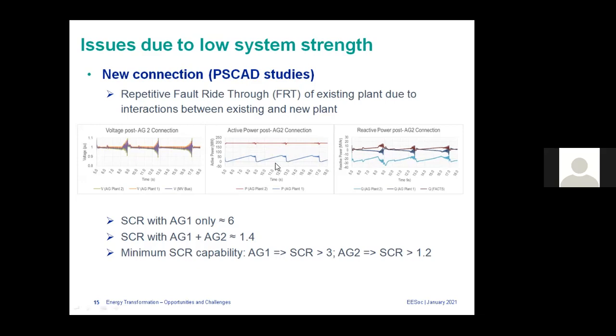You can see in the middle plot that when you model it, the second plant can maintain stable operation. But the first plant goes through repetitive fault ride through. What's happening is that when it is generating, it finds the total SCR is less, so it blocks its operation. Then the megawatts drop, and the system seems to be fine, because what inverters do when there is a system voltage issue is block themselves. When the system voltage recovers, they start to operate again. So it blocks, then it only sees the other plant, the system voltage becomes better, and it thinks the system is fine now for it to go and get wind. So it starts operation again, but it can't sustain, and then it goes back to fault ride through mode. So we call this repetitive fault ride through.